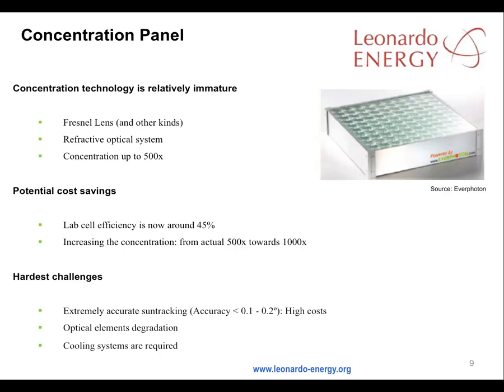Cell efficiencies of 45% are being achieved today in laboratory conditions. At module level, concentrated PV efficiency is around 30%. However, to be effective, the systems rely on sun tracking to an accuracy of less than 0.2 degrees, and they remain expensive. Concentrated light comes with concentrated temperatures, so cooling systems are required, and the optical elements can suffer from quite rapid degradation.